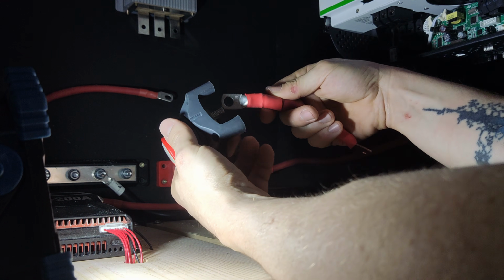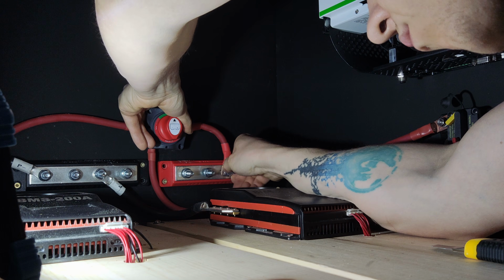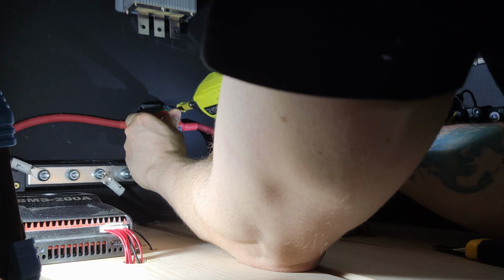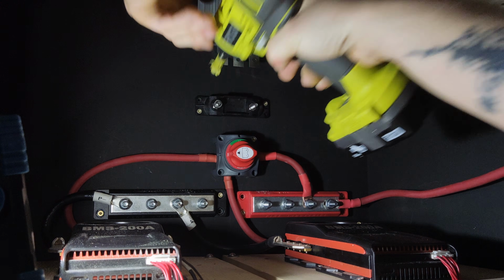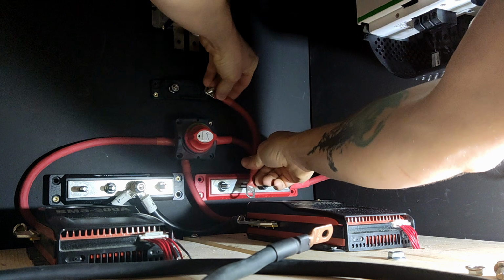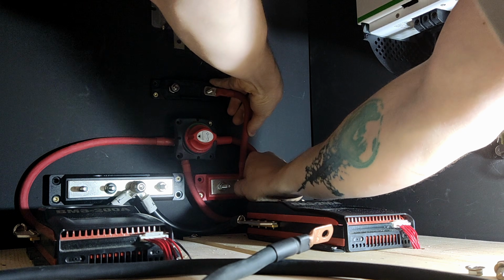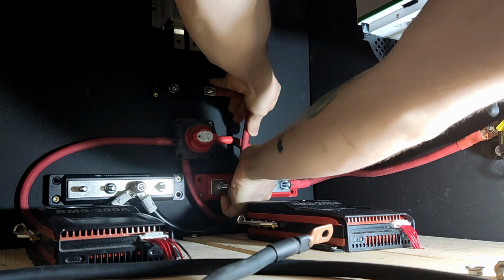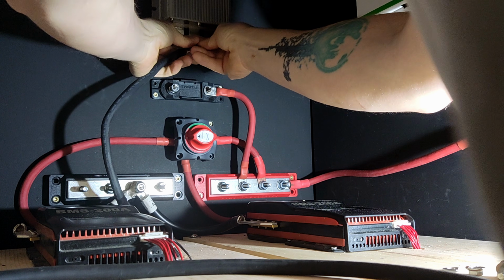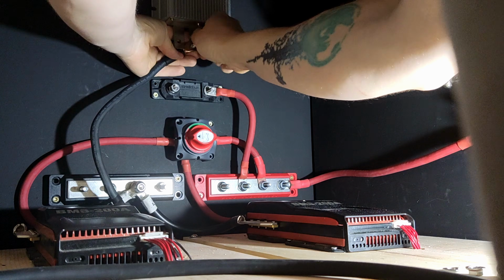Now we can go from the disconnect to the main bus bar. One of the things that's important to keep in mind is that shorter cable lengths are always better in these systems, not only because it's cheaper, but because electricity is less efficient over longer distances of cable runs. So you would actually need a thicker cable for longer runs. Hence the reason why I'm keeping everything as short and efficient as possible here.